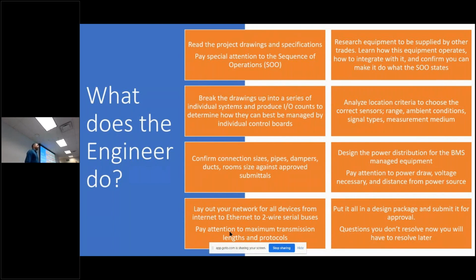Inputs being things like carbon dioxide sensors, temperature sensors, level sensors, airflow sensors, any sensor that is reading some physical medium. We take that into our card and turn it into digital information that I can do something with. How many of those inputs do I need in the system to make the sequence of operation work?